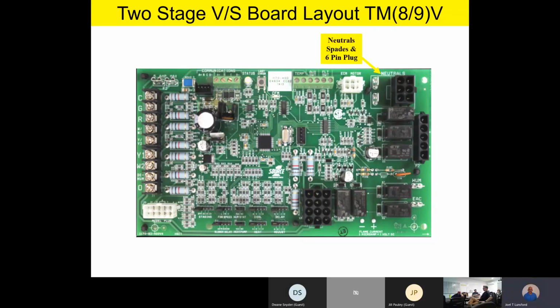Here we have a neutral plug, a 6-pin neutral plug. And you'll also notice beside that 6-pin neutral plug, you're going to have a couple of accessory spade terminals. That's in case you have something, let's say a humidifier or some accessory device that you're going to plug in and you need an extra neutral. So we provide that on the board with our 6-pin plug, but also a couple of accessory neutral spade terminals in case you have an accessory that you want to hook up.